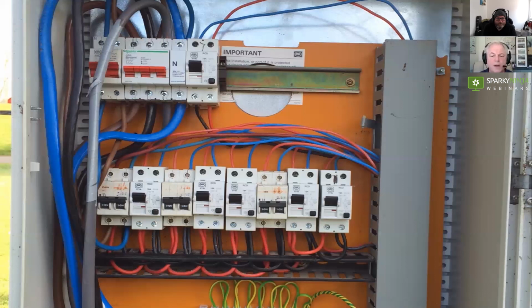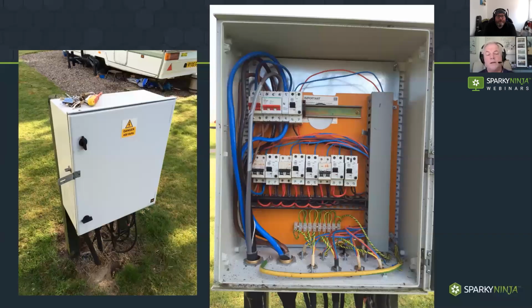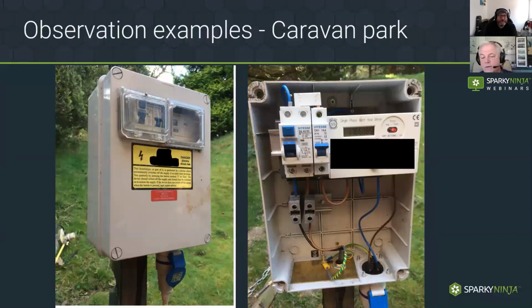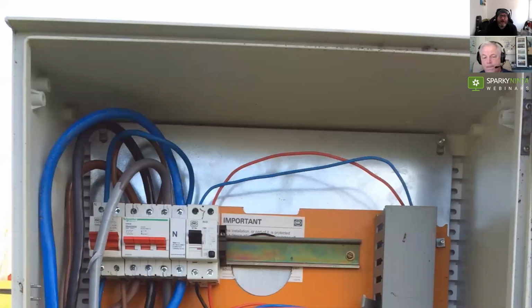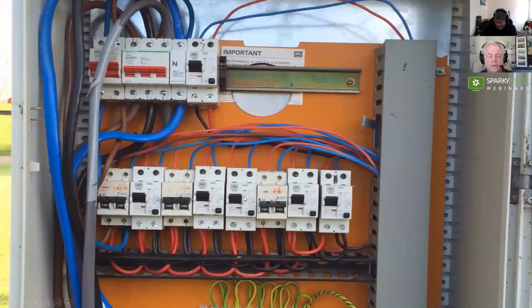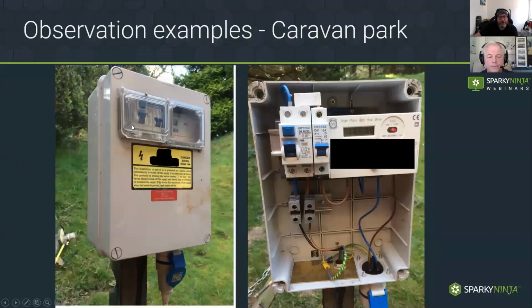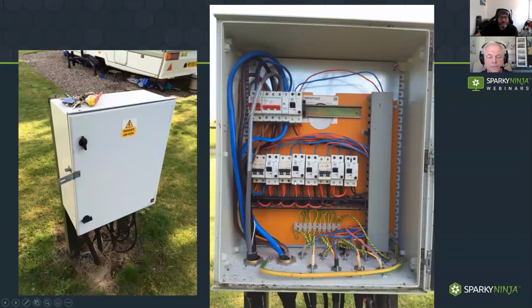One of the guys just made a comment, the fact that if the RCDs trip, you need to access that panel to reset them. So if you access that panel, you've got access to live connections. I mean, none of these are time delayed or anything, are they? No, these are just generic domestic. So there's nothing saying that this will trip independently of one of these. Yeah, and there's no barriers in there. There's no barriers across the live parts. So potential danger there.